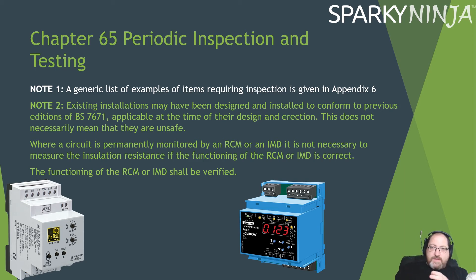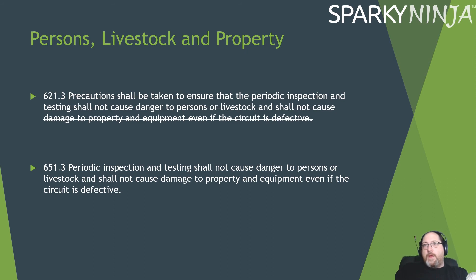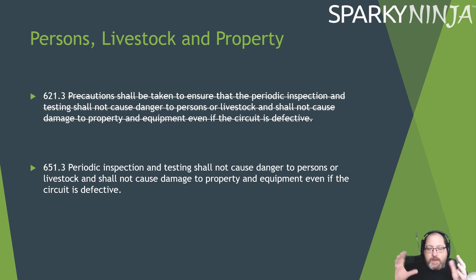So you've got to verify the function of an RCM and the function of an IMD — if they are okay, then the need to carry out insulation resistance tests is removed, because those devices have been doing it for you. Also, 651.3: 'precautions taken' has been changed to 'periodic inspection testing shall not cause danger.' Previously it said precautions shall be taken to ensure it does not cause danger. Now it just says it must not cause danger. The ability to misinterpret what precautions are is no longer there — if you cause danger, that's a non-compliance.